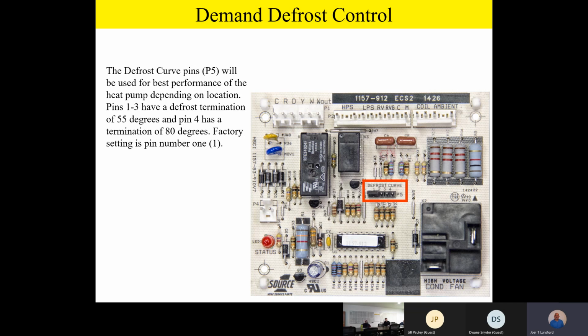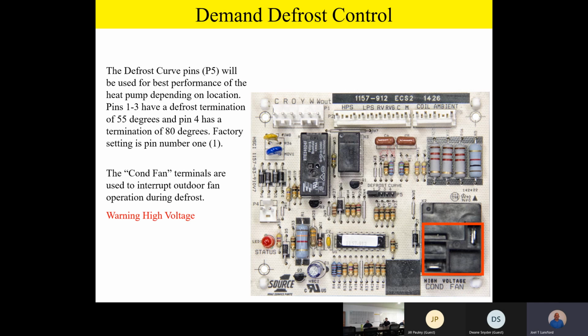Okay, team, as we move around the board, here we have our condenser fan terminals. Please be aware this is the only high voltage spot on the board, so we're going to give you a good warning right here. More specifically, you can see it's a big relay on the board. This is what shuts the outdoor fan off during defrost. So these condenser fan terminals are going to be high voltage, team. Please be careful if you're working on this board.